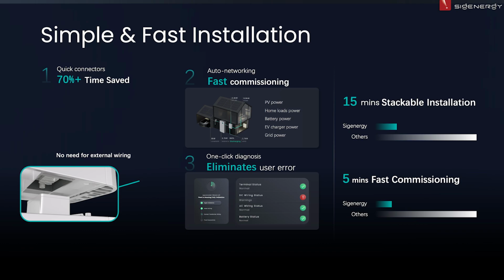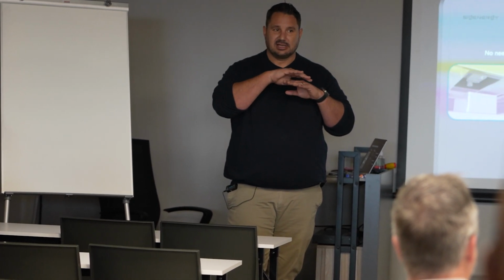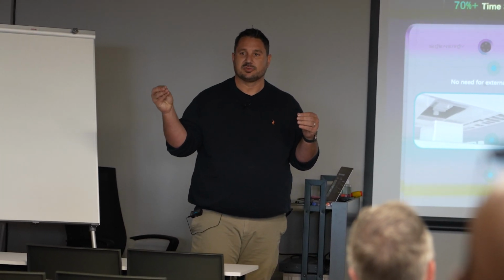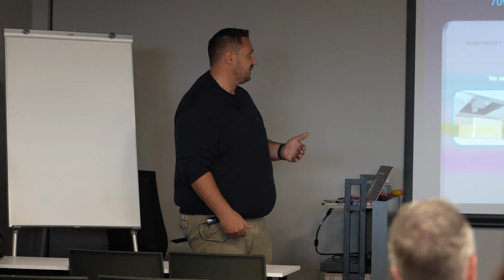It's one-click diagnosis, which means that once you have built the site and you scan the barcode and you want to start commissioning, it will do a diagnosis first and it will say to you, stop, that inverter, that MPPT, you've got the positive and the negative on the DC string the wrong way around. Hang on, inverter 2 on your 3-phase system, you've got a phase rotation error, fix it first. So it'll point out exactly where the fault is before you can commission. So it literally does a scan and sees where the mistakes are, and then those mistakes get reported and it tells you exactly which ones to fix.